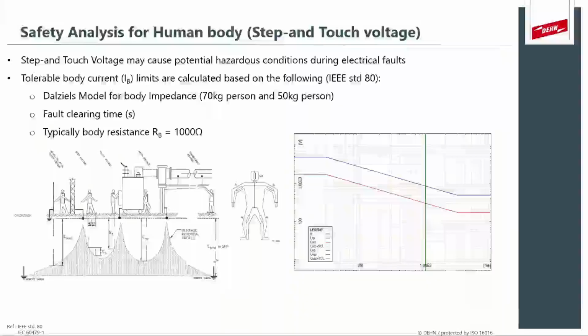Now, to do a quick recap and take a step back, which was explained in previous EasyPower webinars as well, it's just the concept of step and touch voltage. This is extremely important for determining safety in substation areas or lightning protection systems and so on. The hazardous conditions associated with electric shock are based on step and touch voltage in installations like substations and big switching yards and things like that.